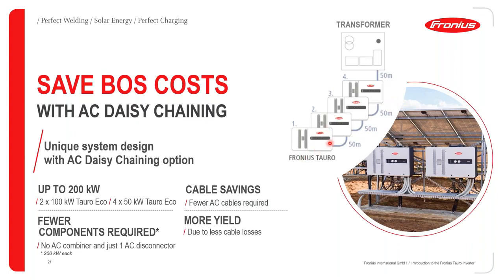But in this case, we are also cutting the cost as far as the distances of the AC cabling are concerned. What you need is just one AC disconnector when you have a power block of up to 200 kilowatts using the Tauro inverter. As far as saving your costs is concerned, that is a very big winner and a point that you should address in your design cases. Also, you will achieve more yield when you're doing AC daisy chaining, due to less cable losses.